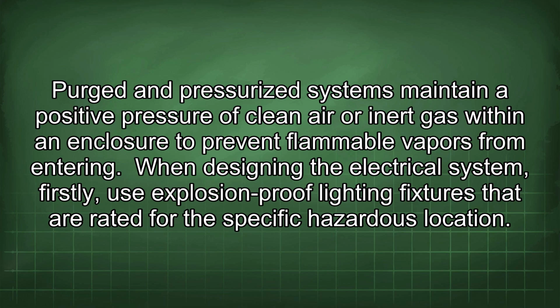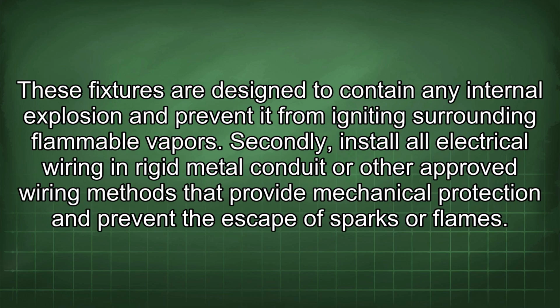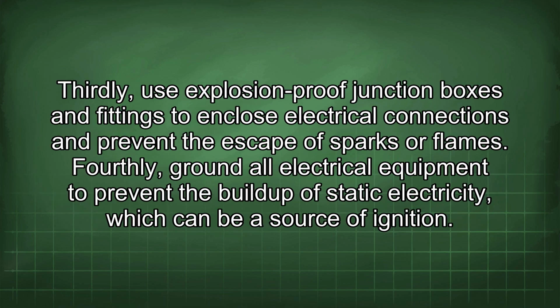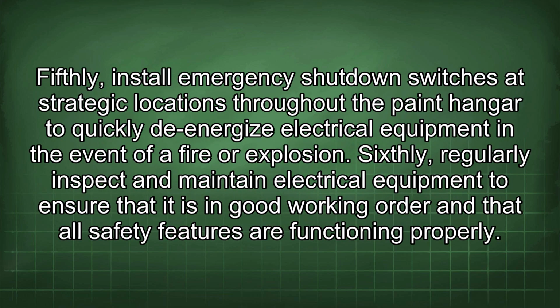use explosion-proof lighting fixtures that are rated for the specific hazardous location. These fixtures are designed to contain any internal explosion and prevent it from igniting surrounding flammable vapors. Secondly, install all electrical wiring in rigid metal conduit or other approved wiring methods that provide mechanical protection and prevent the escape of sparks or flames. Thirdly, use explosion-proof junction boxes and fittings to enclose electrical connections and prevent the escape of sparks or flames. Fourthly, ground all electrical equipment to prevent the buildup of static electricity, which can be a source of ignition. Fifthly, install emergency shutdown switches at strategic locations throughout the paint hangar to quickly de-energize electrical equipment in the event of a fire or explosion.